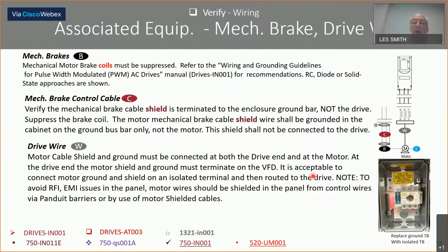Okay, associated equipment, mechanical brake. Here we go. We're going to look at the brake out here. This is actually the coil, the mechanism that moves the brake plates together. Mechanical motor brake coils must be suppressed. And I found that in this article right here. And it says must be suppressed, refer to wiring guidelines. And that one is this guy down here. So it evidently appeared in both. You can use RC networks or diode or solid state on them, however you find the sources.